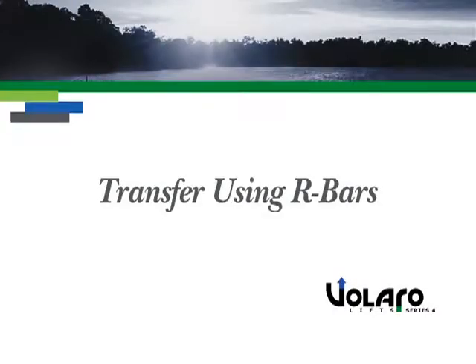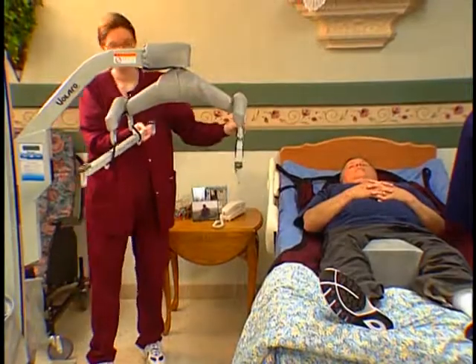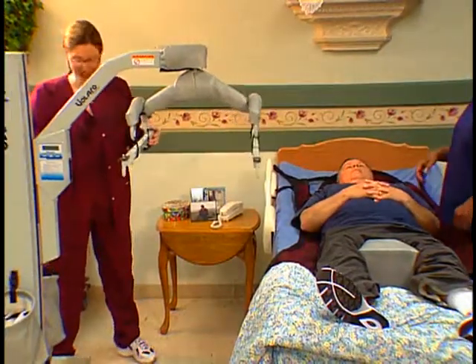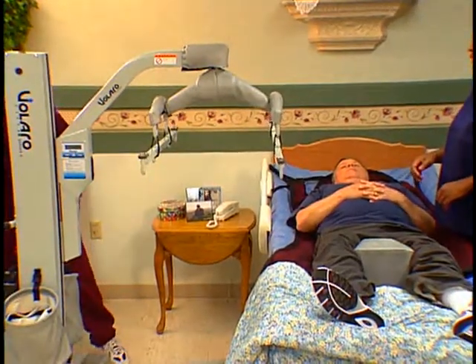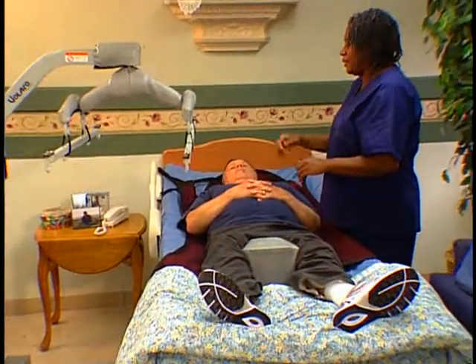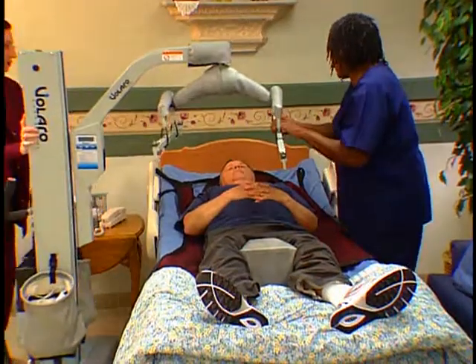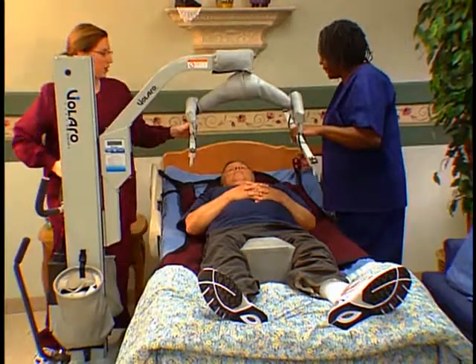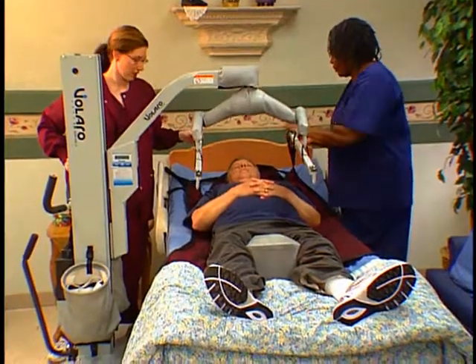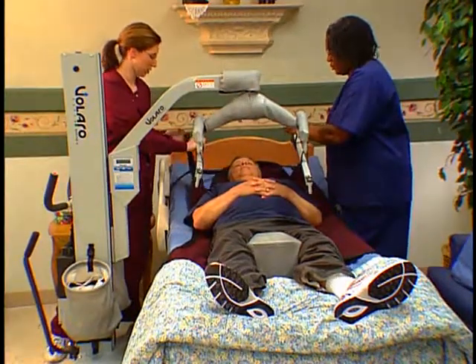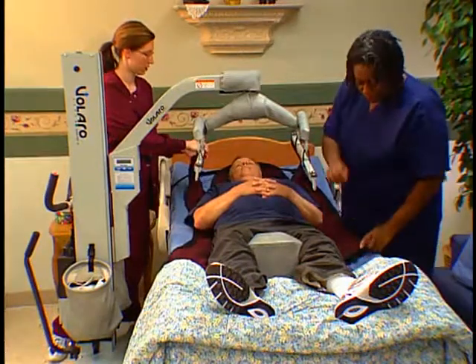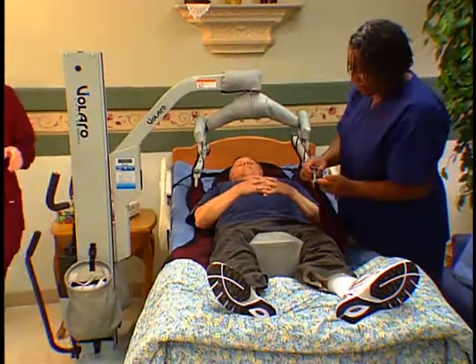Transfers using the R-bars. With the abductor pillow and sling properly placed, you're ready to lift the patient. First, open the legs of the Volaro lift. Next, place the R-bars directly over the patient, using the patient's navel as a centering point. Now lower the lift enough to provide an easy sling hookup. Double check your connections and adjust the head support.